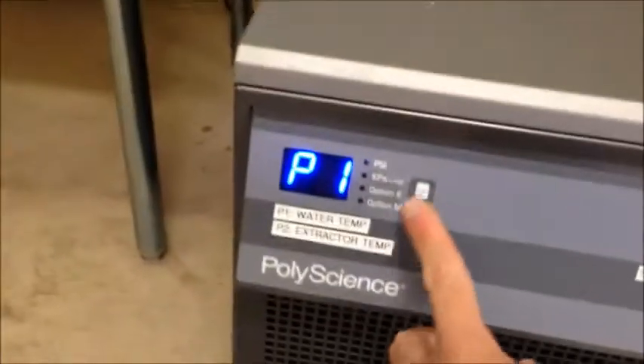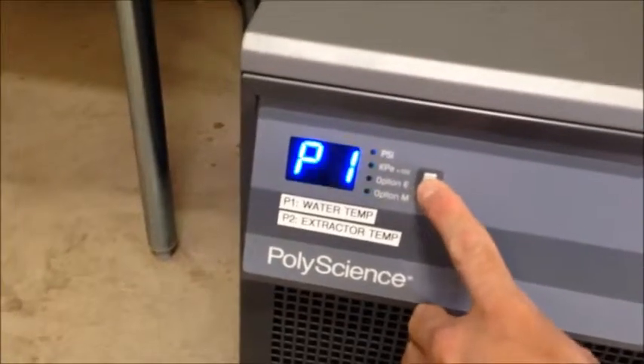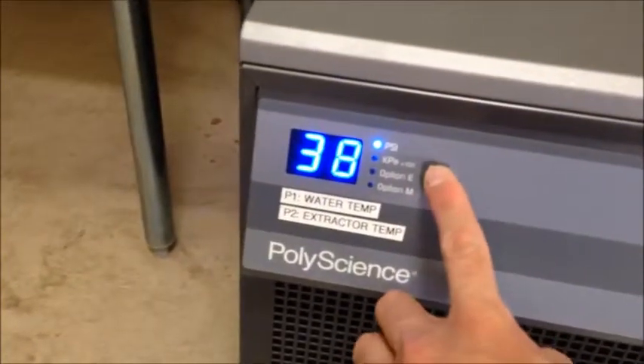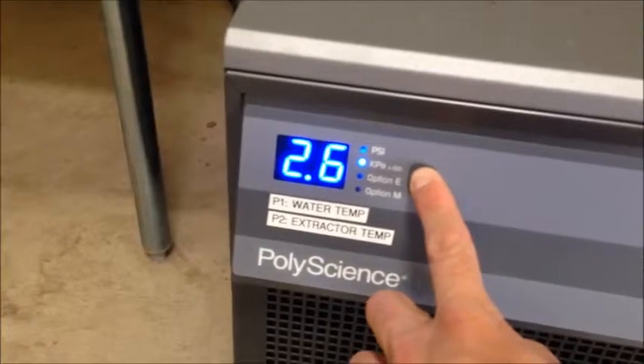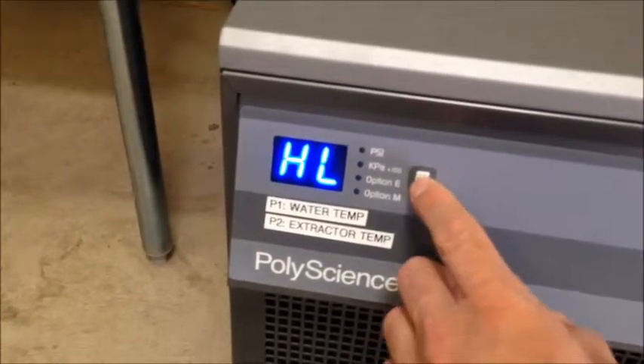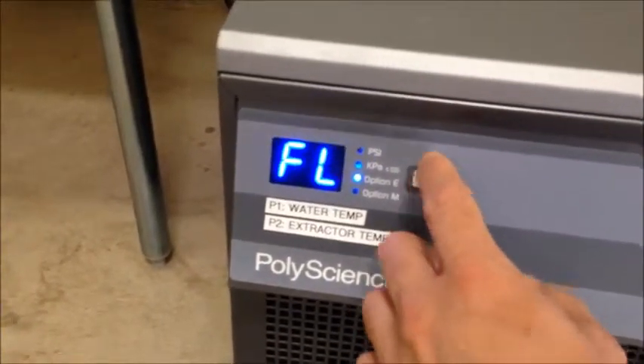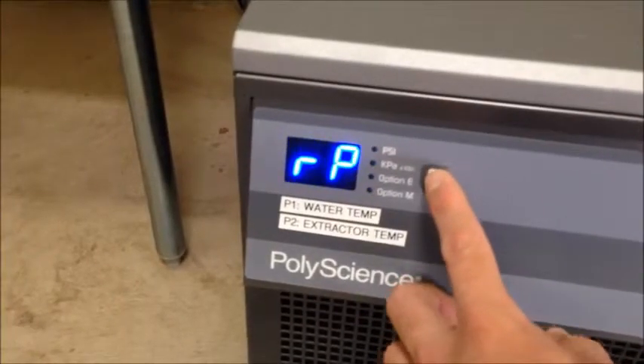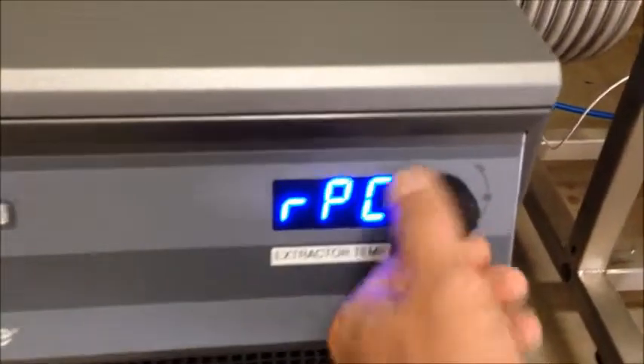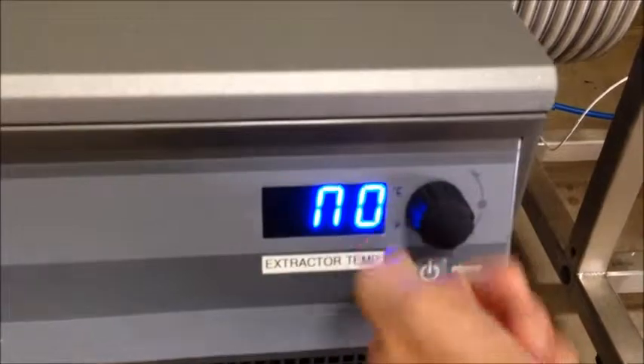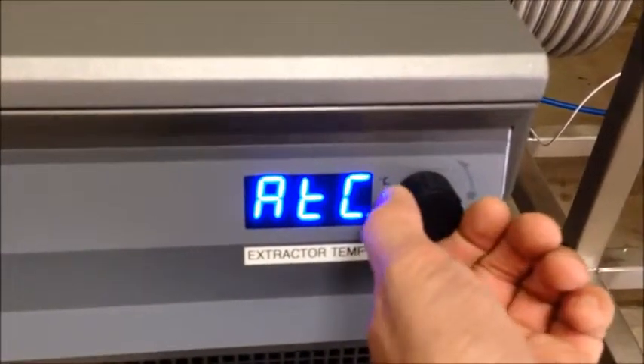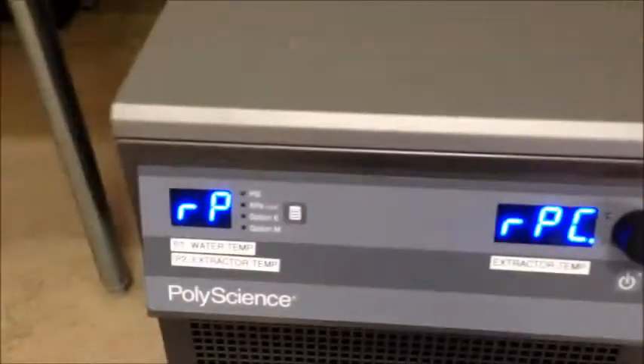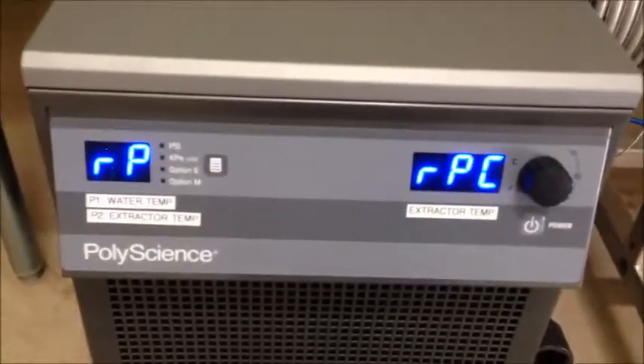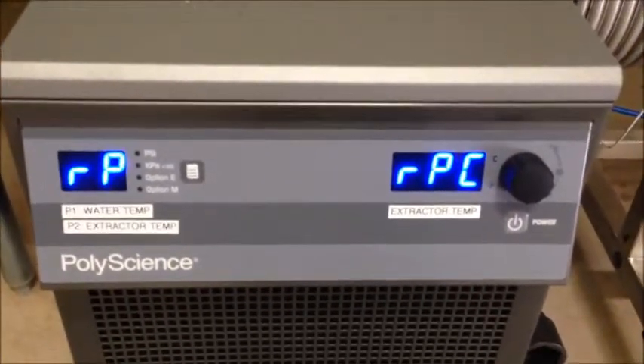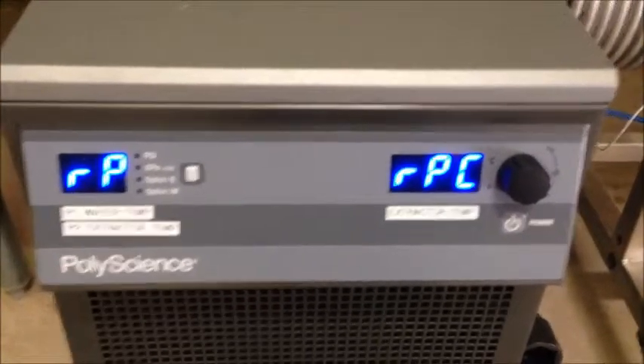If you see a P2, when you scroll through the menu, what you'll do is hold the menu, wait for it to start flashing, and you'll go over to RP, and then ensure that it's on RPC. So yours will probably be on no. You will turn this to RPC. So RP and RPC, then let it sit for 10 seconds. And that will put it to where it reads the remote temperature probe.